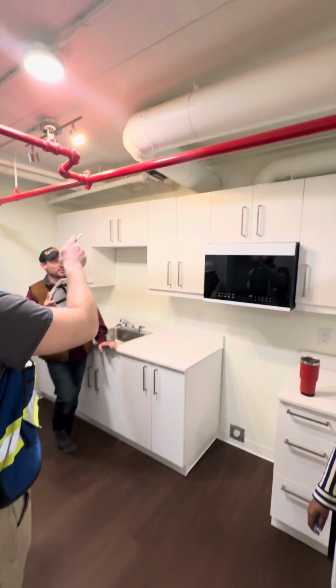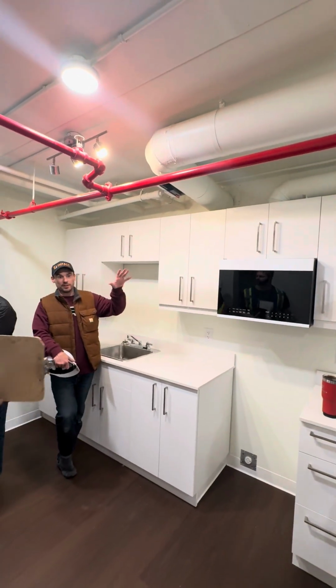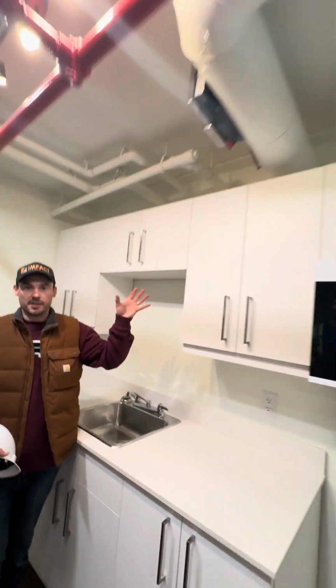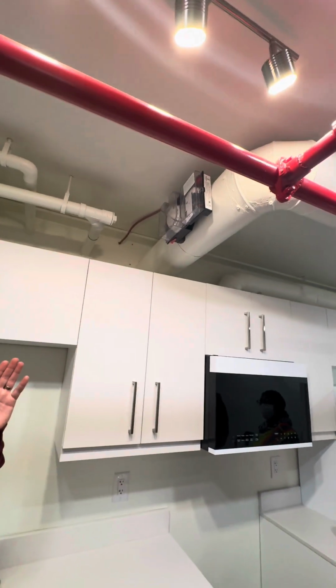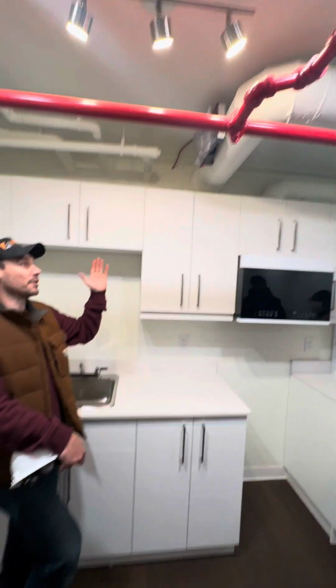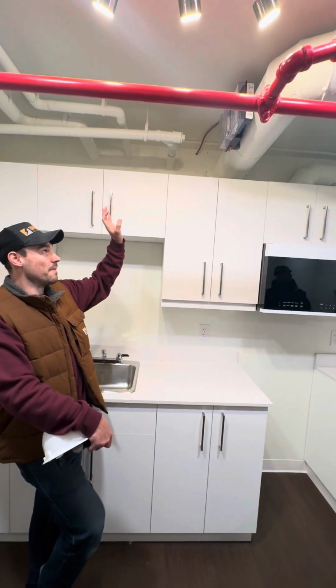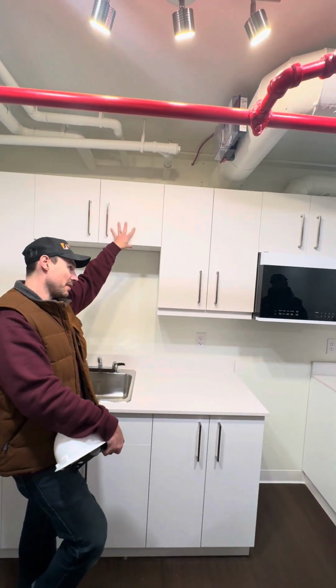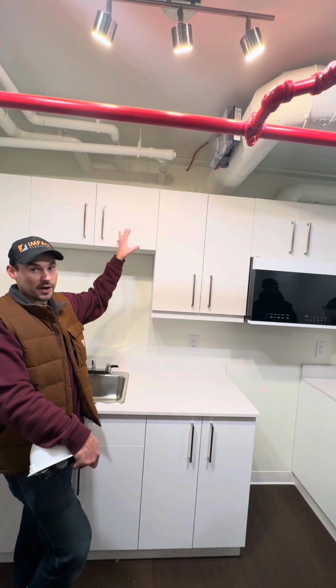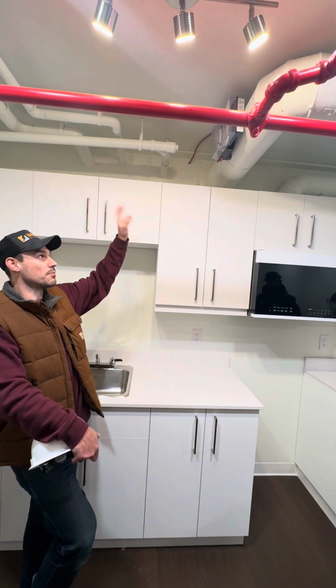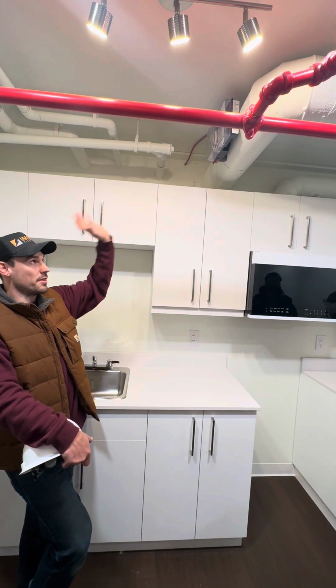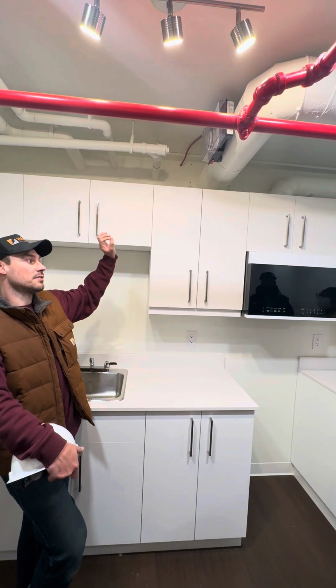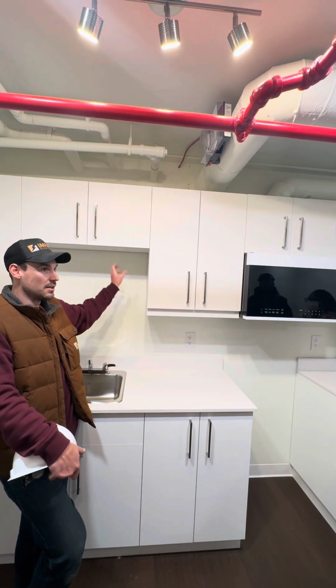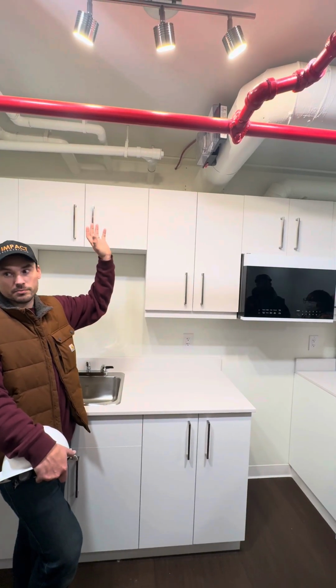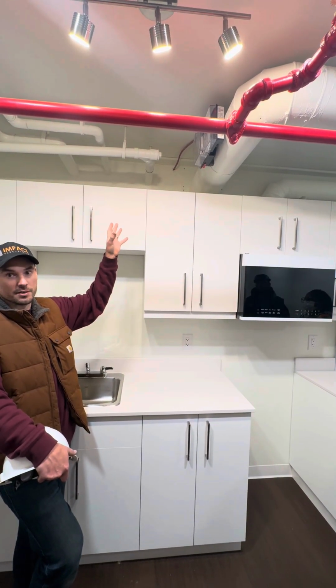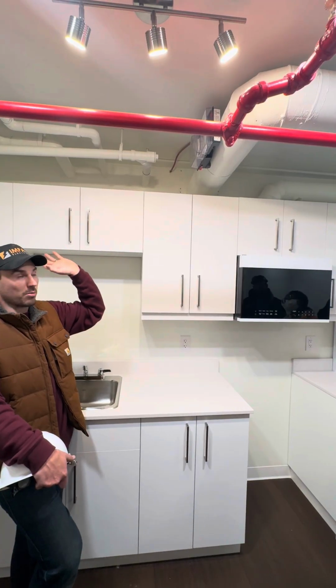With this building, part of the new fire code is that all of the dampers have to be controlled by a duct smoke detector. So every single damper is controlled by a standalone duct smoke. This damper here feeds the next suite over. For code regulations, we had to put a smoke duct detector within 5 feet of it. So this smoke detector in this room is to feed the neighboring suite. It's not a maintainable battery backup smoke. It's part of the actual fire alarm system, so any of these duct smokes are part of the fire alarm system.